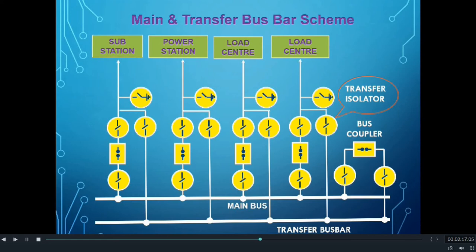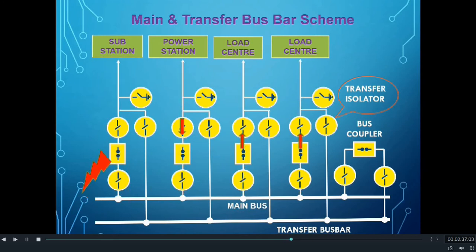Let us see how this scheme works. In normal condition, Main and Transfer Busbar Scheme works like a Single Main Busbar Scheme only. All the feeders are connected to a single Busbar, that is the Main Bus, and the transfer isolators of the feeders are generally kept open. In case of a fault in any one of the feeders — that is, any circuit breaker of a feeder — the feeder becomes out, but all the remaining feeders work normally, which is the same as the Single Busbar Scheme.